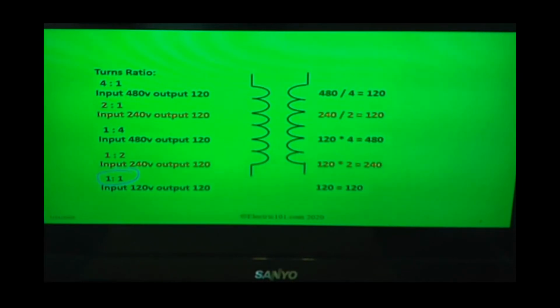There are also a lot of transformers out there that have a 1 to 1 ratio. This is called an isolation transformer. You see a lot of these in control circuits. You see a lot of these controlling computers, drives, PLCs, a lot of different areas. What they're used for is a filter. It filters out a lot of the power quality issues that happen with electrical current. Electrical power is not exactly clean. It actually comes out pretty dirty, especially when it goes through a facility. So if I get 120 volts in, I'm going to have 120 volts out.